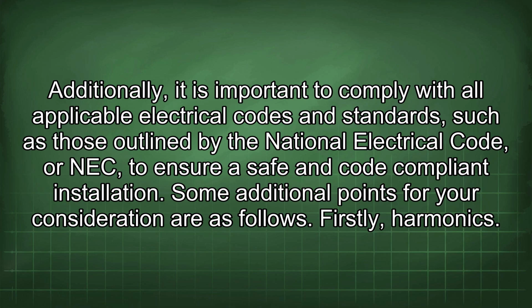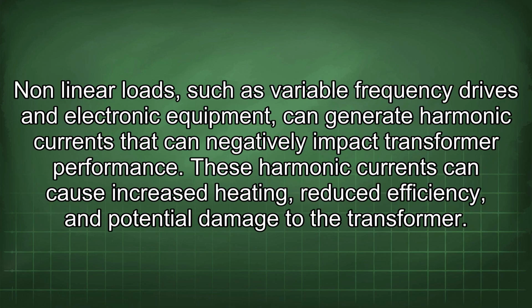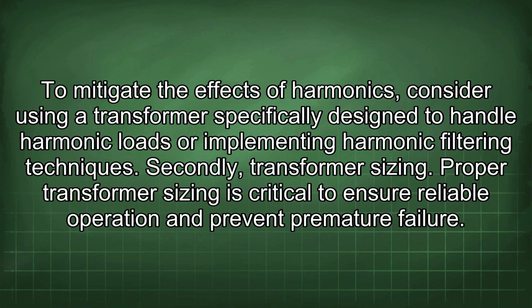Some additional points for your consideration are as follows. Firstly, harmonics. Nonlinear loads, such as variable frequency drives and electronic equipment, can generate harmonic currents that can negatively impact transformer performance. These harmonic currents can cause increased heating, reduced efficiency, and potential damage to the transformer. To mitigate the effects of harmonics, consider using a transformer specifically designed to handle harmonic loads or implementing harmonic filtering techniques.